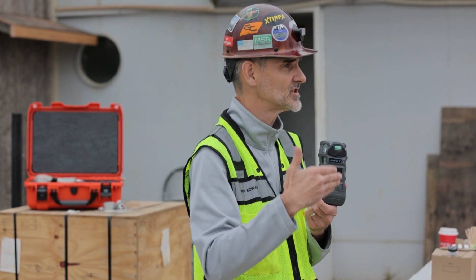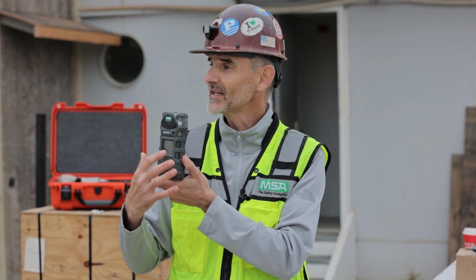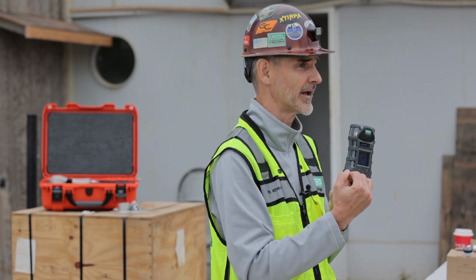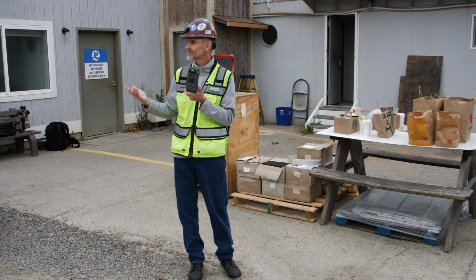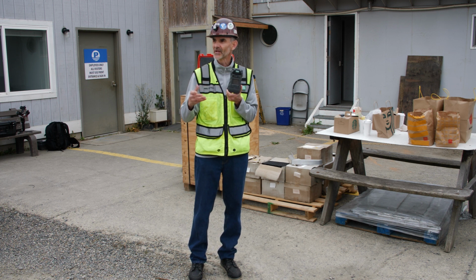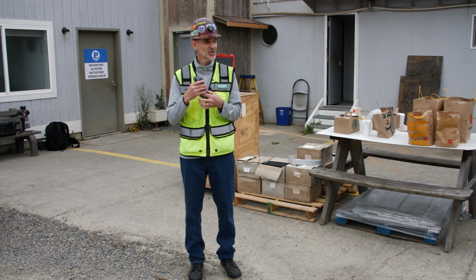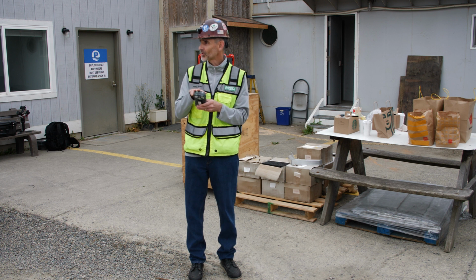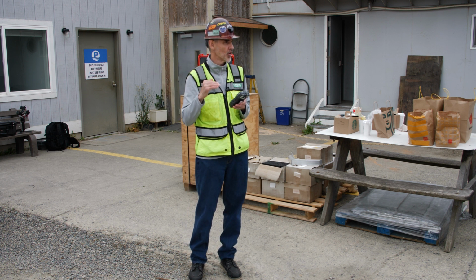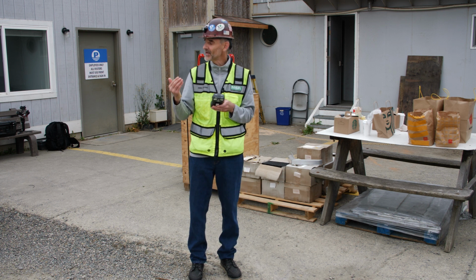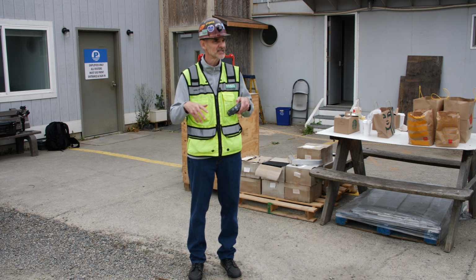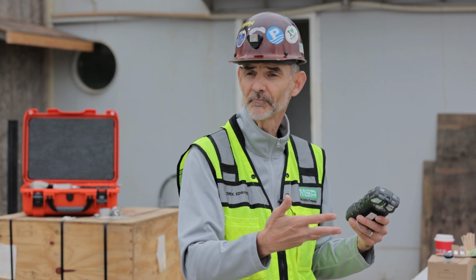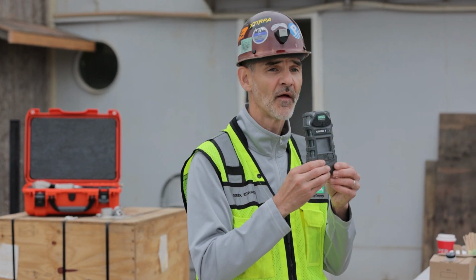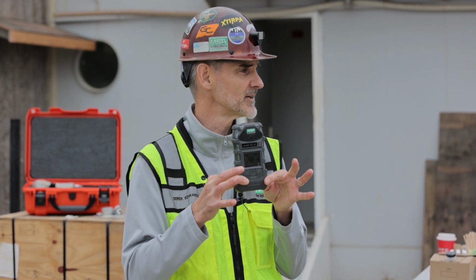You press it again, it's going to show you the minimum screen, which is the oxygen level, okay? I just pushed it twice and it shows me that my oxygen level went down to 18%. If we continue to press that button, it shows us the date and the time and a bunch of other information that you really don't need. But if you have an alarm, just remember, push the left button. That's going to tell you what sensor went into alarm and how high or low that alarm was. That's important information because if it was CO, now we know we have CO in the space. We need to ventilate, get that out of there. If it's oxygen, again, we need to ventilate, introduce oxygen into the space. Other than that, you really don't need to push the buttons on the instrument except to test the instrument, which we'll do here in a second. Okay?